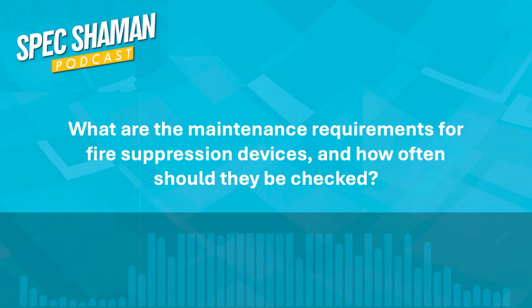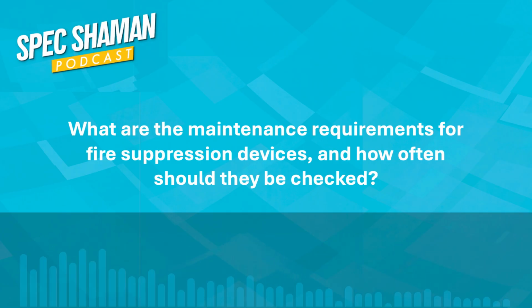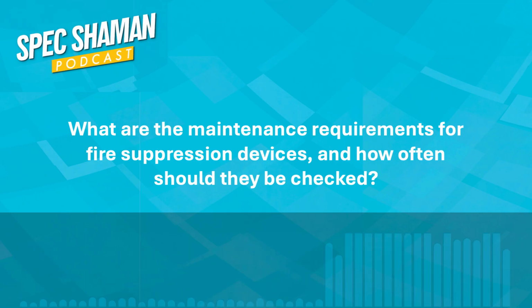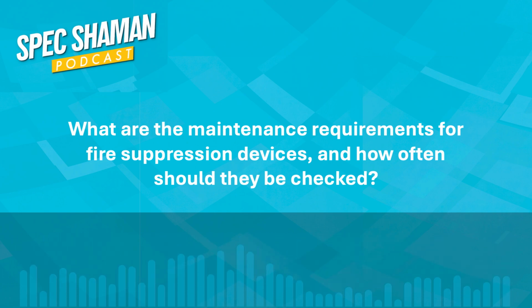What are the maintenance requirements for fire suppression devices, and how often should they be checked? In my opinion, they should be checked every day. Some devices out there, like the canister type I mentioned, there's no way to know if it'll ever work because it just sits there, and you hope that if the fuse catches fire, the firecracker inside explodes and the panels open up, dumping out baking soda. Same thing with the one that uses a smoke sensor for activation, you hope the smoke sensor reads the fire early enough to turn off the power and dampen the flame, but you don't know.